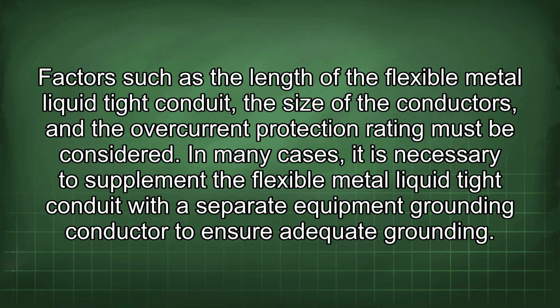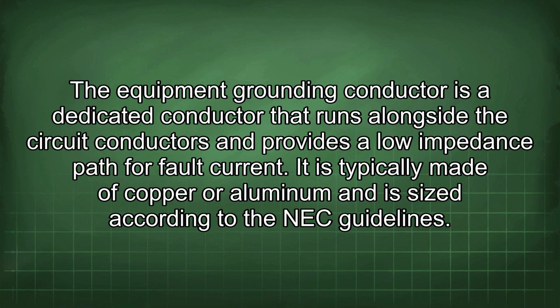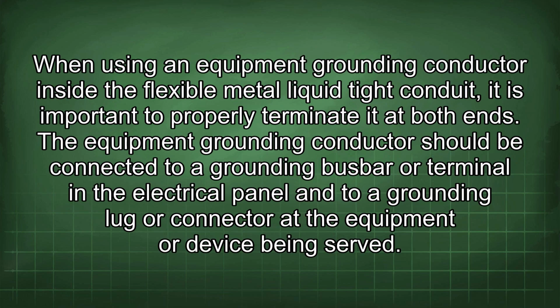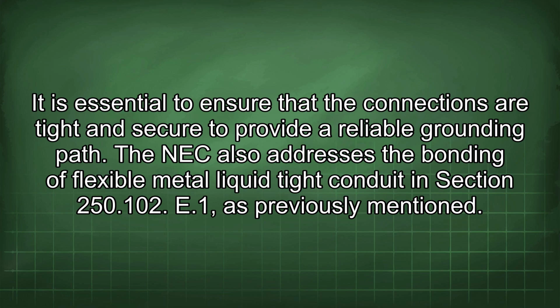In many cases, it is necessary to supplement the flexible metal liquid tight conduit with a separate equipment grounding conductor to ensure adequate grounding. The equipment grounding conductor is a dedicated conductor that runs alongside the circuit conductors and provides a low impedance path for fault current. It is typically made of copper or aluminum and is sized according to the NEC guidelines. When using an equipment grounding conductor inside the flexible metal liquid tight conduit, it is important to properly terminate it at both ends. The equipment grounding conductor should be connected to a grounding busbar or terminal in the electrical panel and to a grounding lug or connector at the equipment or device being served. It is essential to ensure that the connections are tight and secure to provide a reliable grounding path.